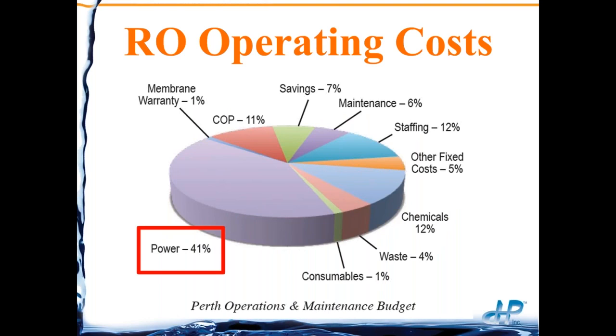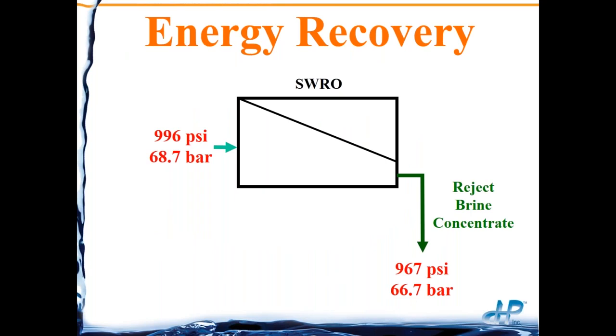As most of you are probably aware, power is the single biggest operating cost of an RO unit. So anything we can do to reduce power is going to reduce the life cycle cost of RO. If we look at a seawater RO system, it can be over 1,000 psi — over 70 bar — to force that water through the membrane. When you look at the concentrate, there's very little pressure drop. Energy recovery is where we recover the pressure and energy of the reject brine or concentrate stream, and use that energy to help pressurize the feed.